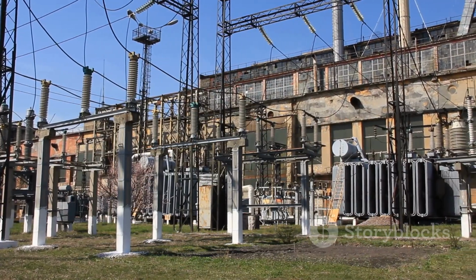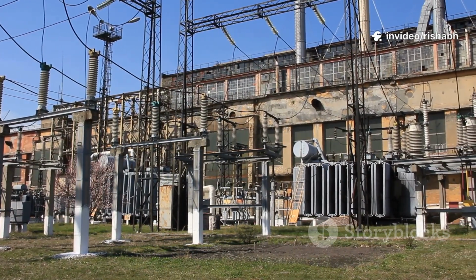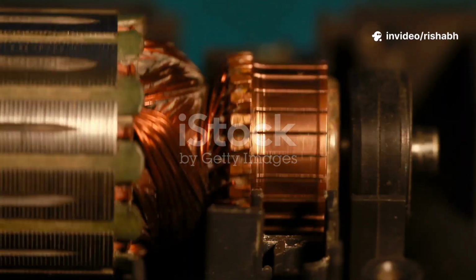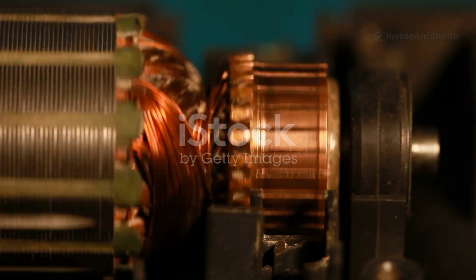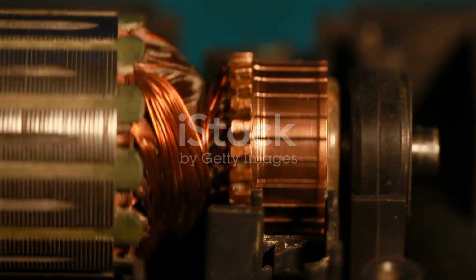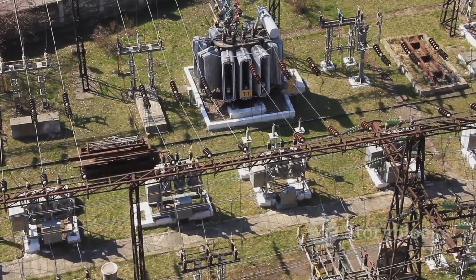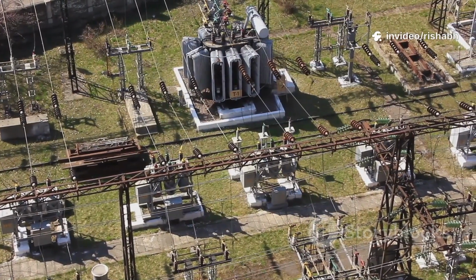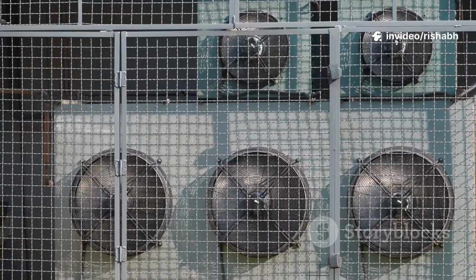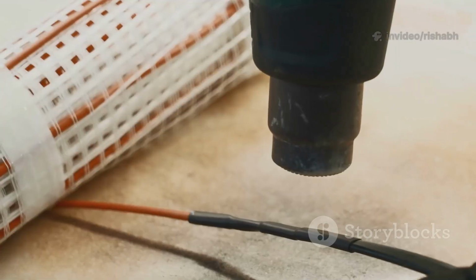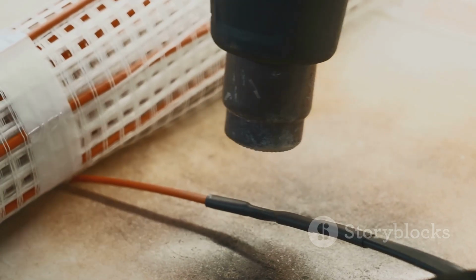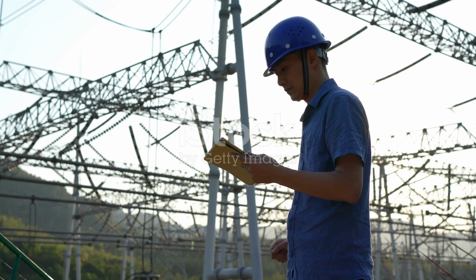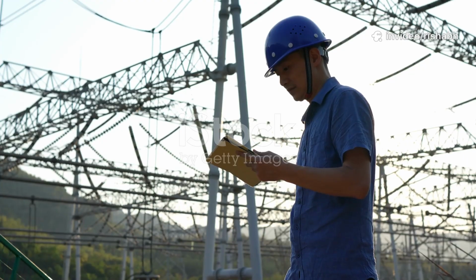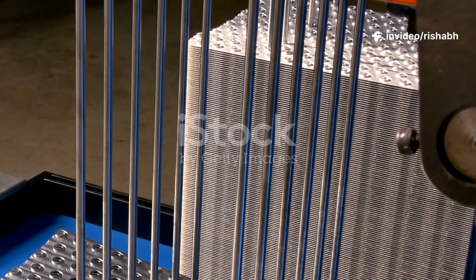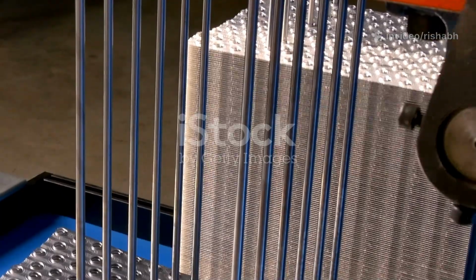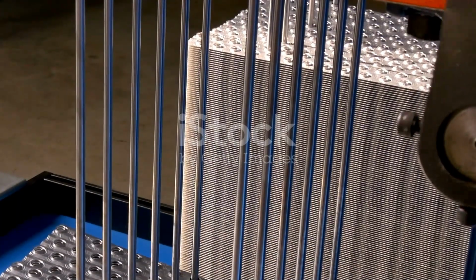A power transformer is a highly efficient machine, but it's not perfect. Losses in the core and windings, though small in percentage, generate a significant amount of heat in a large MVA unit. A 500 MVA transformer might generate a megawatt of heat, enough to power a small neighborhood. This heat must be continuously removed. If the internal temperature gets too high, the paper insulation will rapidly degrade, drastically shortening the transformer's life.